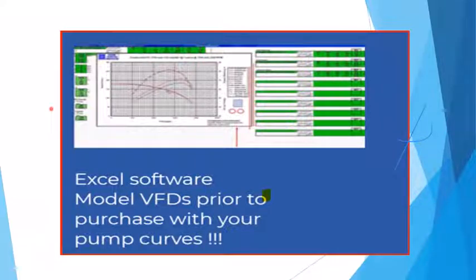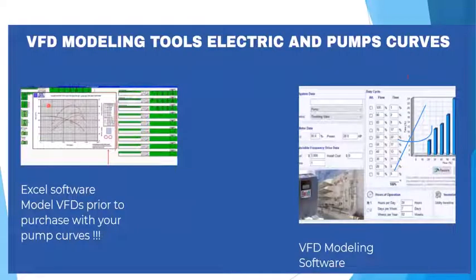It's a little different in a process where we're basically just controlling speed and power to maintain a certain pressure. VFDs in a high-rise building tend to have a bit more advantage. But definitely we've got to look at the total harmonic distortion. There's also VFD modeling software available. I can get that to you for free. You send me an email and I can get you access to this software, which I think is very good in the marketplace and can also help.